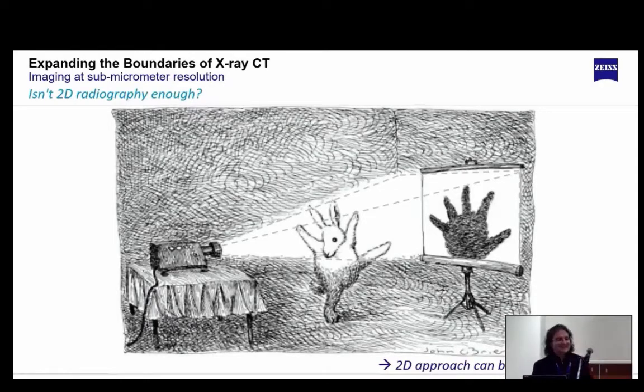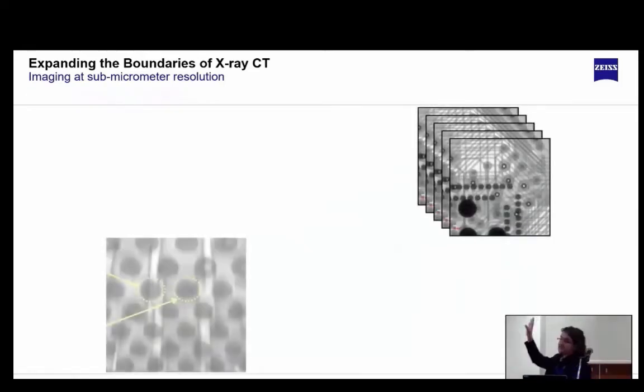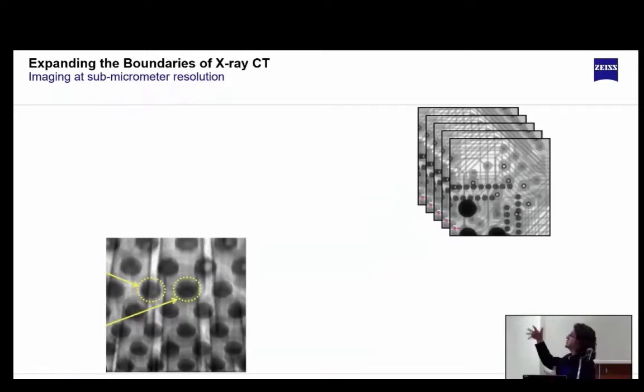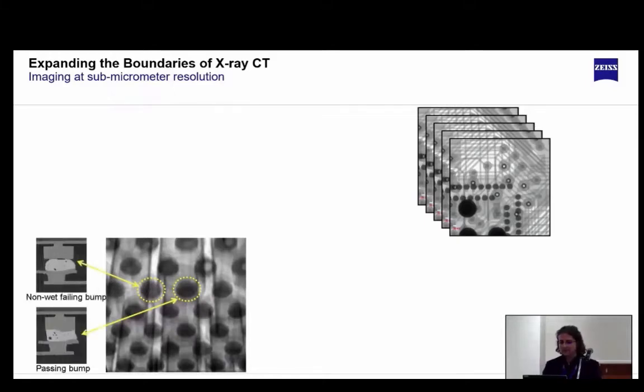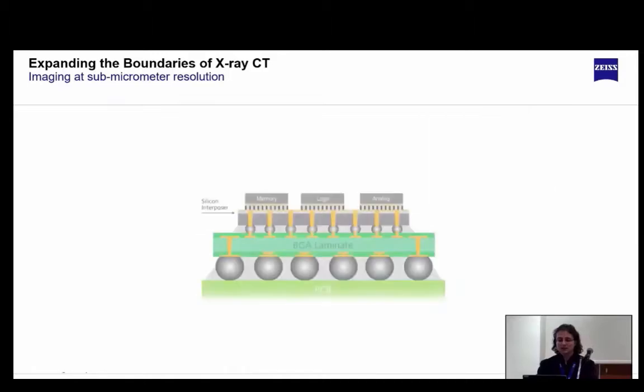So the 2D projection can be misleading, and we can see it from this example. It's because in radiographic projections you have the back layers and the front layers, and you might see a low density that might look like a void, but you are not quite sure. And even if you think it's a void, you don't know exactly where it is in space. So by using 3D X-ray computed tomography, you can actually slice virtually in the 3D volume and see if those are actually voids or not, or any other kind of defect. So that's the main advantage of having 3D information.